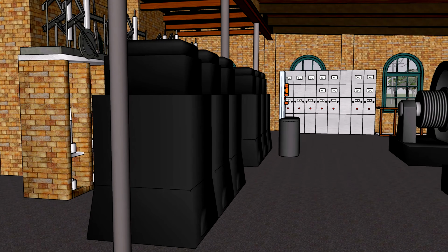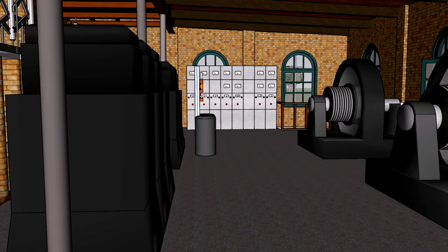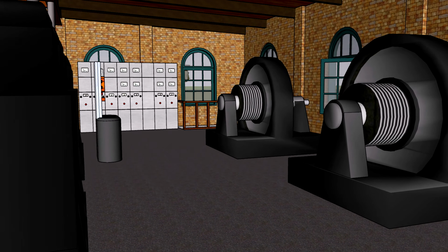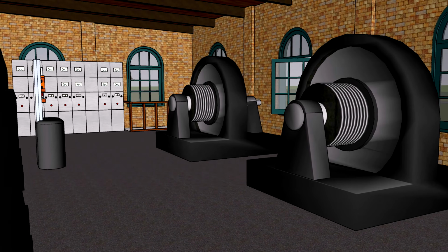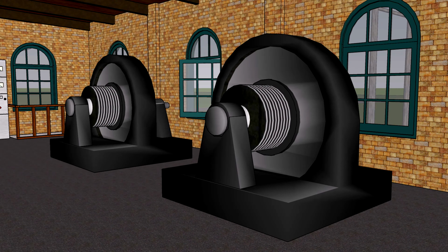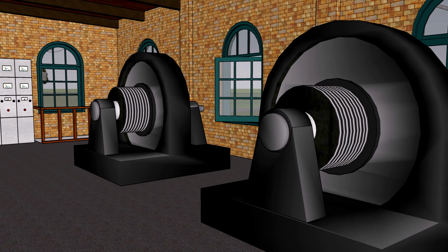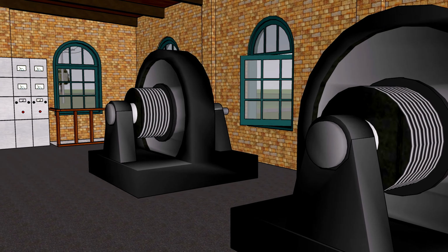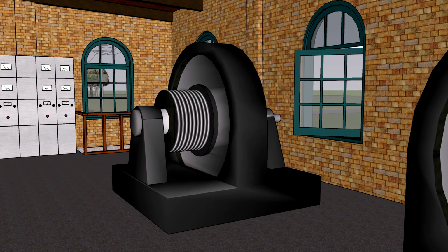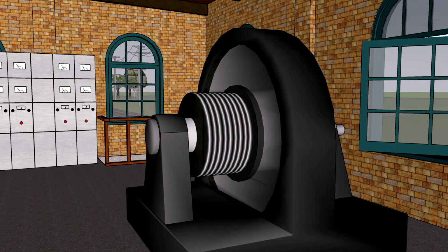The two massive rotary converters to the east of the building were also General Electric equipment. Each substation was designed to hold up to 3 of these converters, each generating 500 kilowatts of continuous direct current. The Clintonville station always had at least 2 of these 500 kilowatt converters, possibly sometimes having 3 units during the heaviest workloads around 1910. These converters were based on a 6-phase alternating current, spun at 1500 RPM, and weighed 20 US tons apiece. It's no wonder that the main room's concrete floor required additional brick walls in the basement in order to carry the weight.